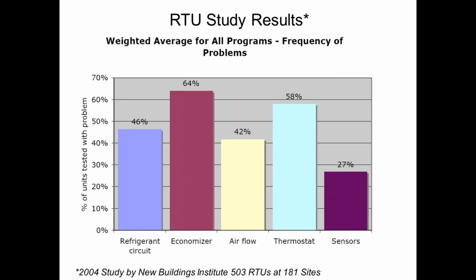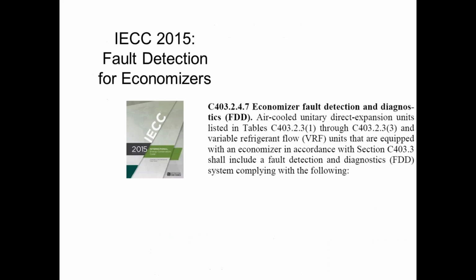Because of stuff like this, the code folks have started paying attention to the fact that we told you to put these economizers in, they're supposed to save all this energy, but if half of them aren't working correctly, what's the point, right? So now the code actually has a requirement where these things have to babysit themselves and track if there's a problem. So economizers, all economizers, need to have fault detection and diagnostics, FDD. That's been a universally adopted acronym, and as you know in our world, if there's an acronym, it's real.